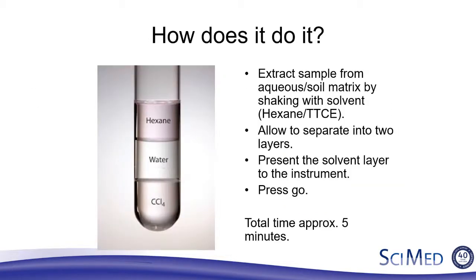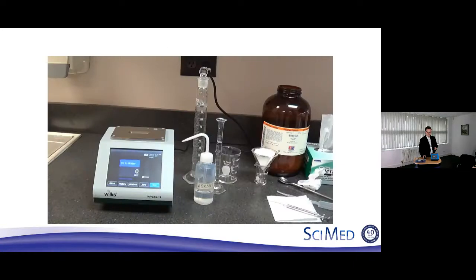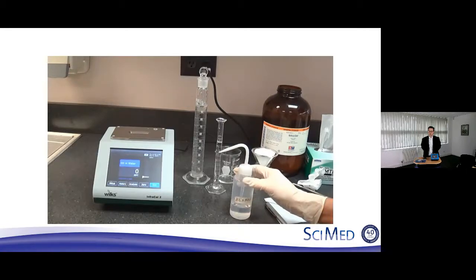Like those other techniques, we do a solvent extraction. We have the choice of using a solvent lighter than water — hexane — or a chlorinated solvent which is heavier, depending on how we want to prepare our sample. My personal preference is hexane because it sits on top and is easy to sample from. It has a very quick sample preparation time of around five minutes, which I'll show you shortly. On the bench you can see the InfraCal along with everything you need: a wash bottle of hexane to clean the top of the instrument between every sample.